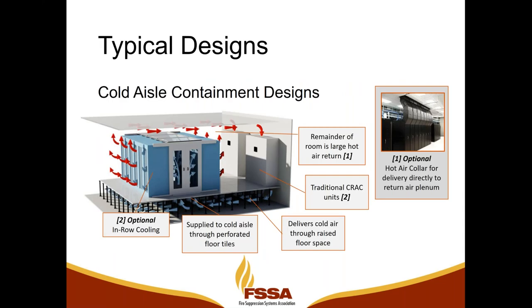Cold aisle containment designs still often use raised floor systems. Another trend we're seeing is fewer data centers being built with raised floor, but sometimes in a cold aisle containment system, the cold air will be ducted right into the cold aisle and we will still contain that. And so that air is forced through the server equipment and out the hot side of the server racks into the room.